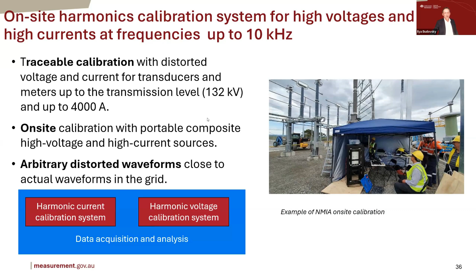Here's, for example, a diagram of the harmonic voltage calibration system, which contains a composite source that can provide 100,000 volts of fundamental frequency plus 1,000 volts of harmonics up to 10 kilohertz. We use the same techniques to calibrate the capacitive divider, which is the reference for the high voltage harmonic system, and we already started calibrating voltage harmonics, voltage transformers, and also current transformers. There's a similar system up to 4,000 amps, where 1,000 amps would be harmonics that are the exact replica of what one can find on the network.